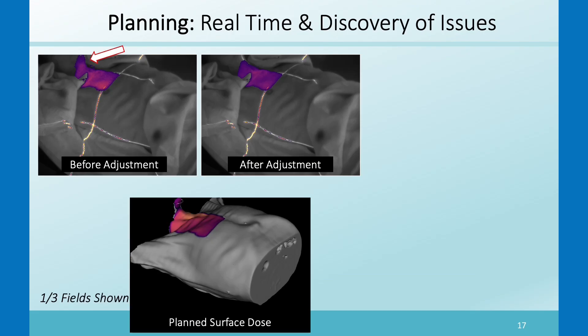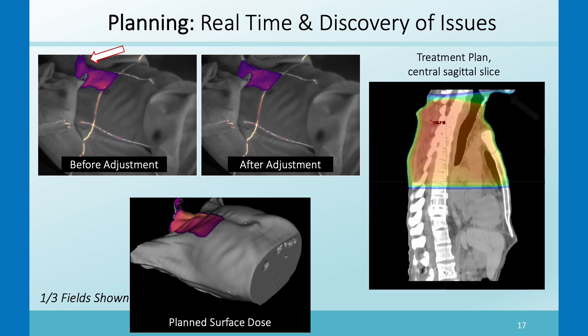Another case shows a patient with the beam a little high on the chin. The therapist actually saw it in the Cherenkov image, went in, and asked the patient to lift their chin higher. Here is the beam after correcting the chin position. Subsequently, we went into the treatment plan and actually saw that the plan had been created with the chin down a little bit and the beam in the chin, which was not ideal.